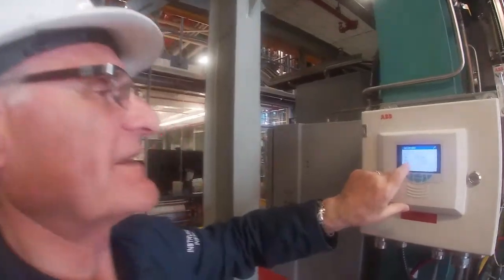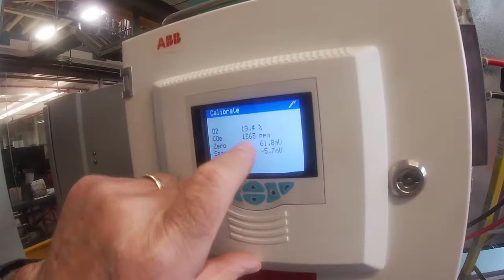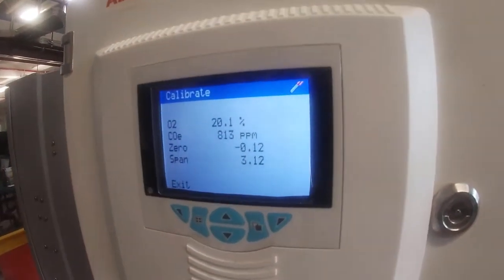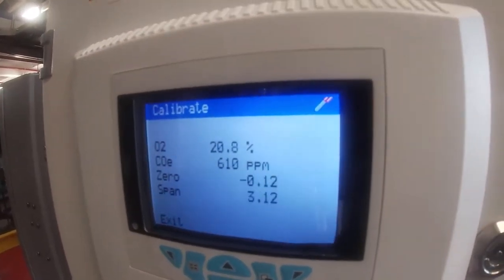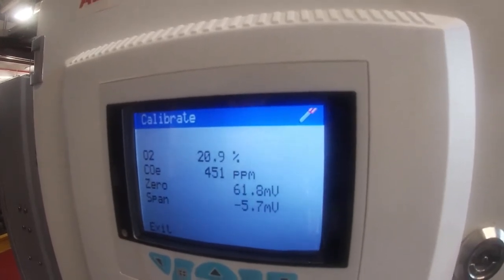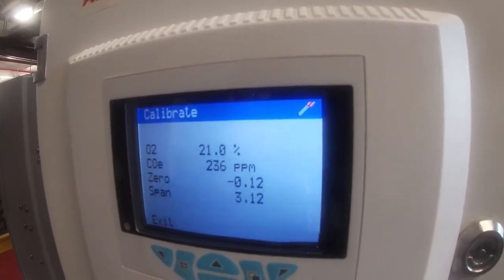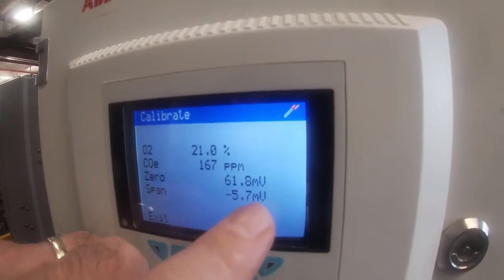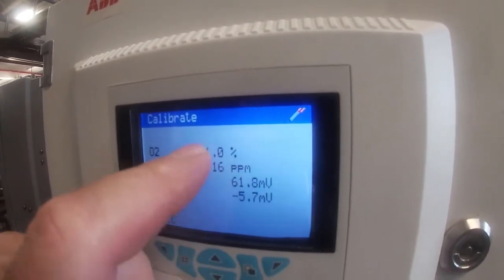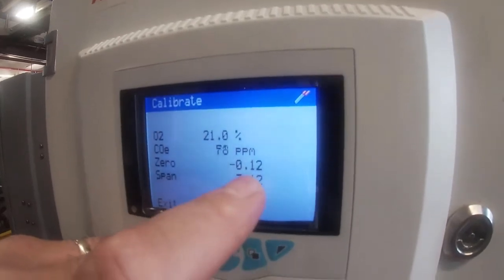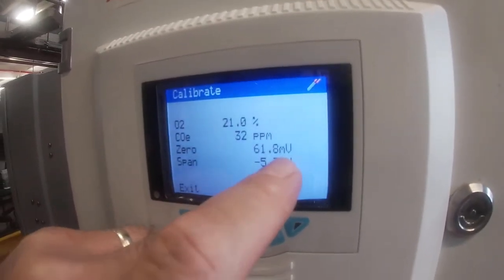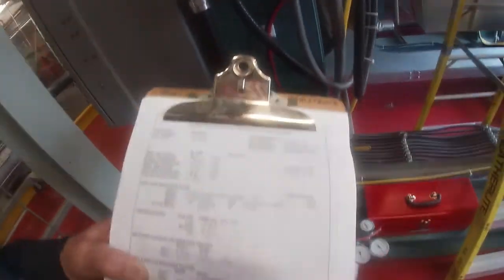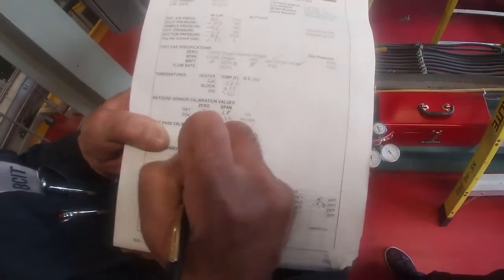Okay, now what's happened is that it's going through and it's telling us what the actual calibration values were for 0 and span. And so we're on our O2. Let's just see right now. That's CO. This is what is really happening, and this is our span, and this is O2 values. So the O2's 0 value is sitting at, let me get right, 61.8, and his span is minus 5.7.